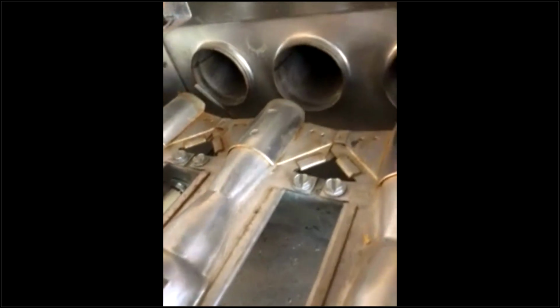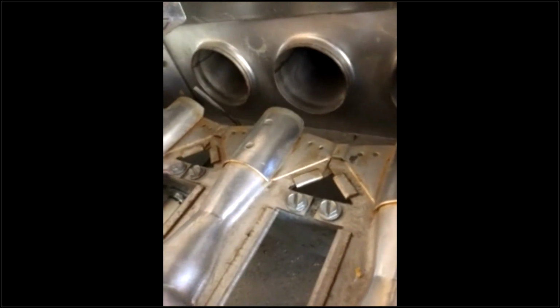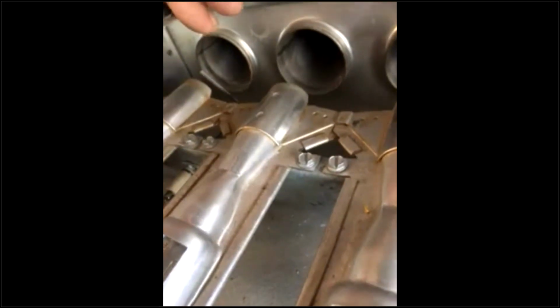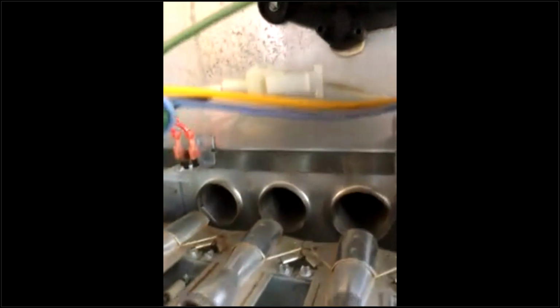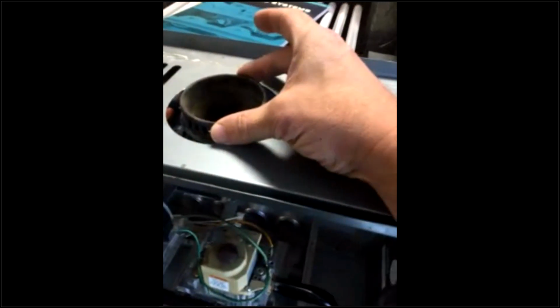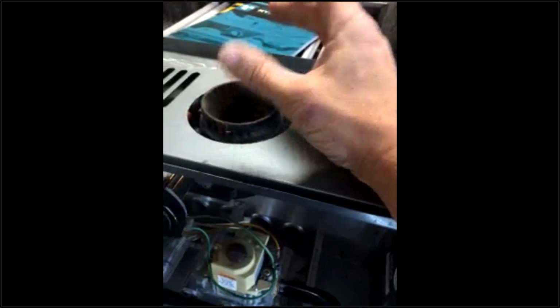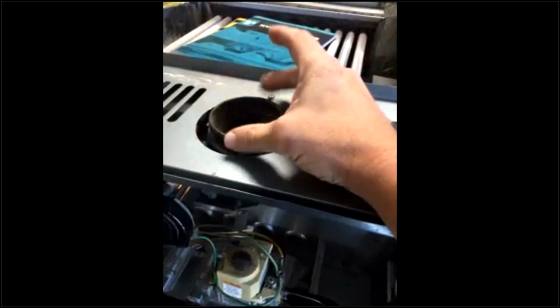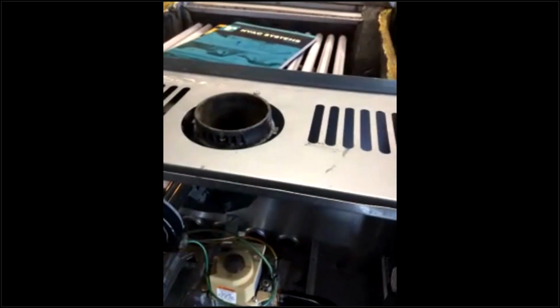And there's a sensor there. There's the rod, flame sensor. Let's see, it's right there. There's a temperature limit switch there, looking for flame rollout, essentially. It's right there. And the draft inducer fan. And there's that one concern about the connection between the vent pipe, metal pipe, and this area here.